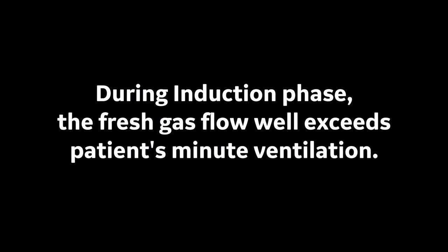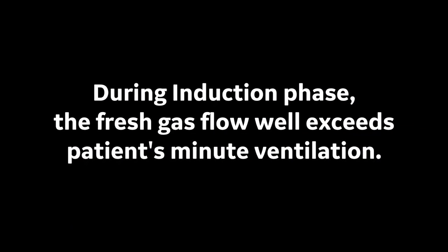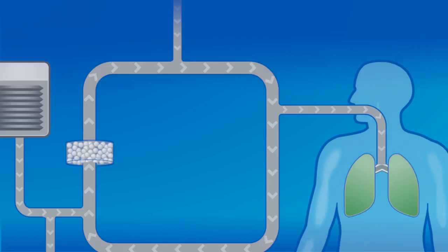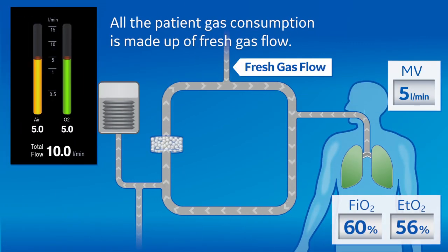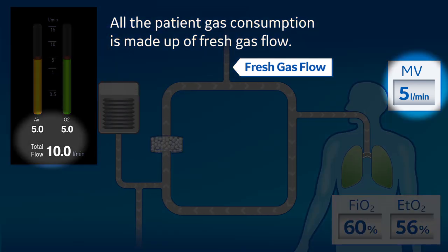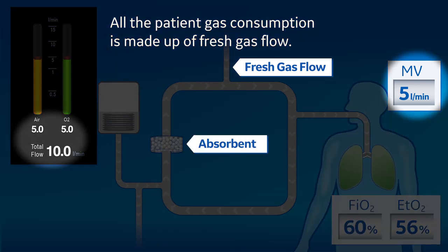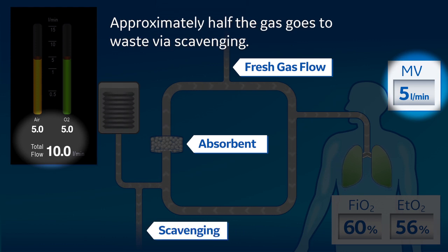During the induction phase, the fresh gas flow well exceeds the patient's minute ventilation. All the patient's gas consumption is made up of fresh gas flow. Approximately half the gas goes to waste via scavenging.